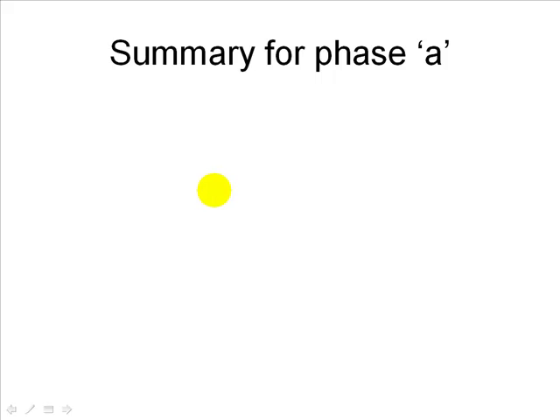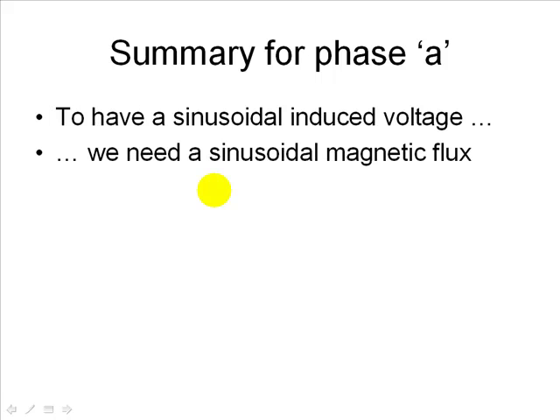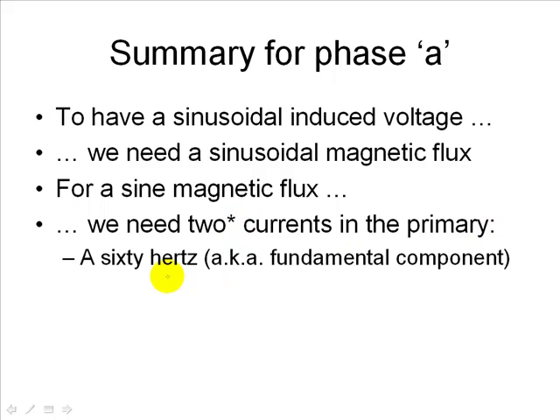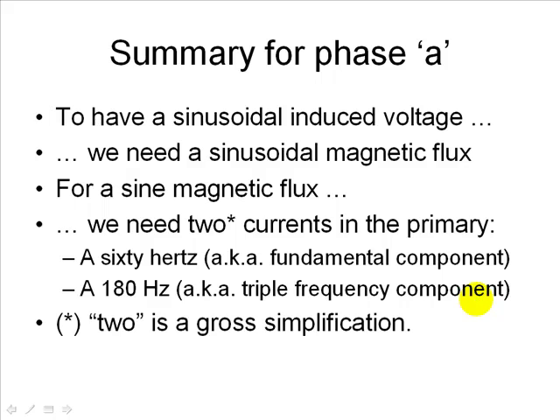Let's summarize for phase A. To have a sinusoidal induced voltage in the coils, we need a sinusoidal magnetic flux. But for a flux that is changing sinusoidally with time, we need two currents in the primary. A 60 Hz current, also known as the fundamental component of the magnetization current, and a 180 Hz current, the triple frequency component. As I said before, two is an approximation.